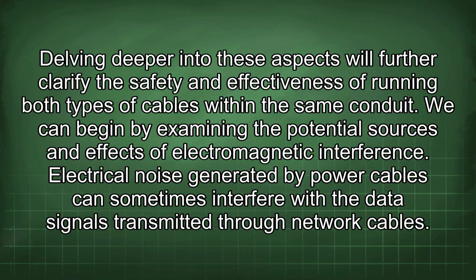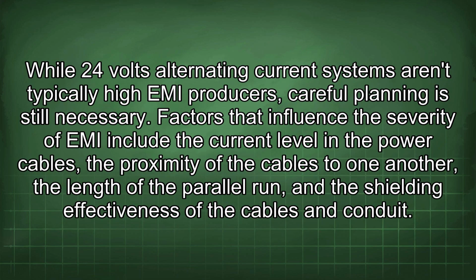Delving deeper into these aspects will further clarify the safety and effectiveness of running both types of cables within the same conduit. We can begin by examining the potential sources and effects of electromagnetic interference. Electrical noise generated by power cables can sometimes interfere with the data signals transmitted through network cables. While 24 volts alternating current systems aren't typically high EMI producers, careful planning is still necessary.